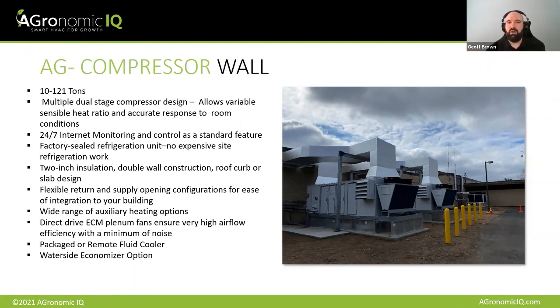We can tailor our capacity to it very, very tightly. And there's a couple of quote unquote weird things about these units that are done for a very good reason. One, they're all water cooled or glycol cooled. We have a package configuration available for all of the units, or they can be done as site splits or split fluid cooled units. But we're using a glycol cooler because it allows us to completely isolate the refrigeration circuits, those small pods that I talked about, from what's happening outside.